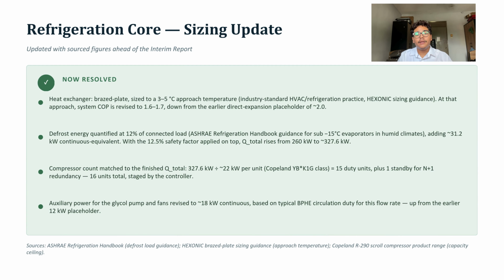So the good news: the assumptions that we made earlier from the prior slide are now closed with real numbers, not placeholders. First, the heat exchanger. We sized it to a 3 to 5 degree approach temperature, which is standard practice for this kind of equipment. That gave us a real efficiency number, a coefficient of performance of 1.6 to 1.7. Slightly lower than a direct system would have, but it is an honest cost for keeping the flammable refrigerant outside.